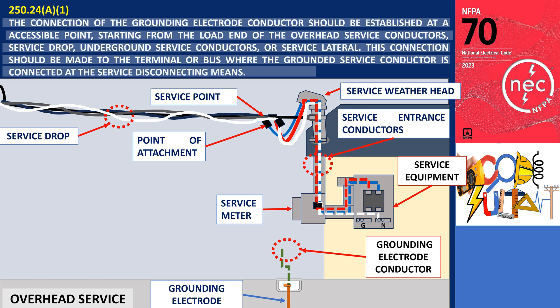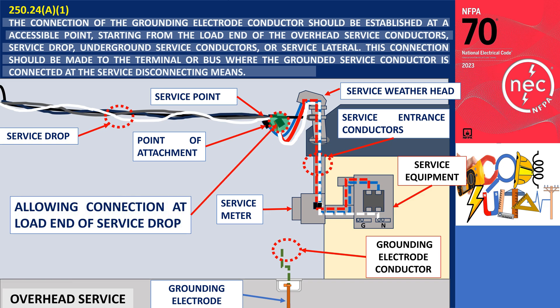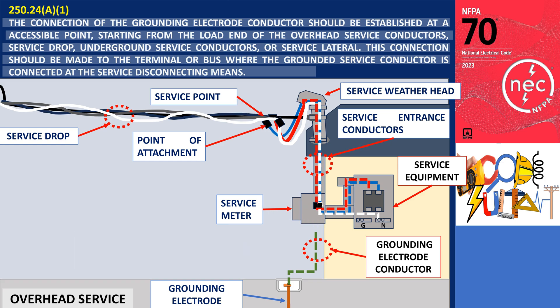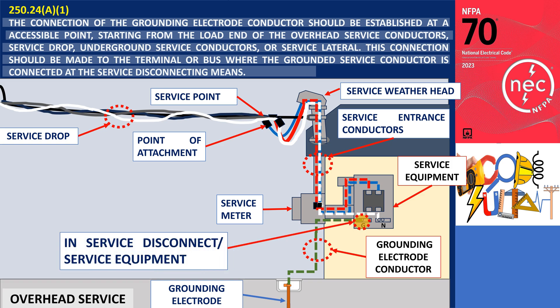In an overhead service installation, the grounding electrode conductor connection should be made at a convenient and accessible point — typically at the load end of the service drop or service conductors, which includes components such as the weatherhead, meter socket, or current transformer enclosure. However, the specific location may require approval from the authority having jurisdiction due to a utility seal on the metering enclosure. Alternatively, the connection can be made within the service equipment enclosure, which is the most commonly accepted location by AHJs.